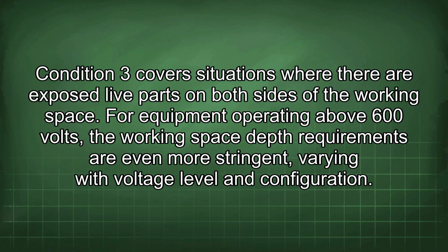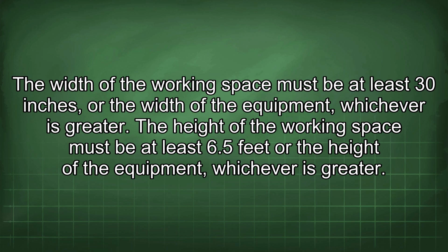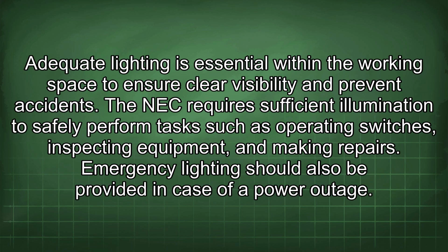For equipment operating above 600 volts, the working space depth requirements are even more stringent, varying with voltage level and configuration. The width of the working space must be at least 30 inches, or the width of the equipment, whichever is greater. The height of the working space must be at least 6.5 feet, or the height of the equipment, whichever is greater. Adequate lighting is essential within the working space to ensure clear visibility and prevent accidents. The NEC requires sufficient illumination to safely perform tasks such as operating switches, inspecting equipment, and making repairs. Emergency lighting should also be provided in case of a power outage.